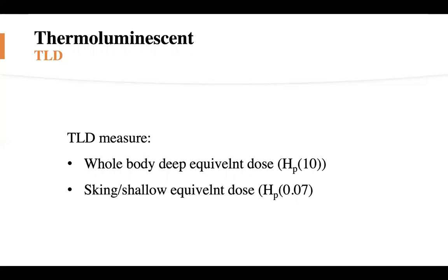Do you know what HP10 means? TLD also measures the shallow dose equivalent, HP 0.07. The whole body deep equivalent dose is the equivalent dose measured at 10 millimeters under the surface exposed to radiation. This is just more explanation about this number, okay.